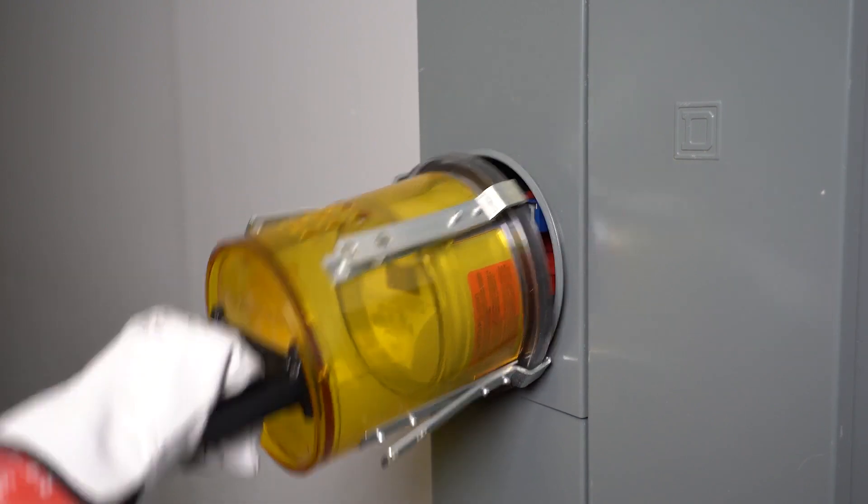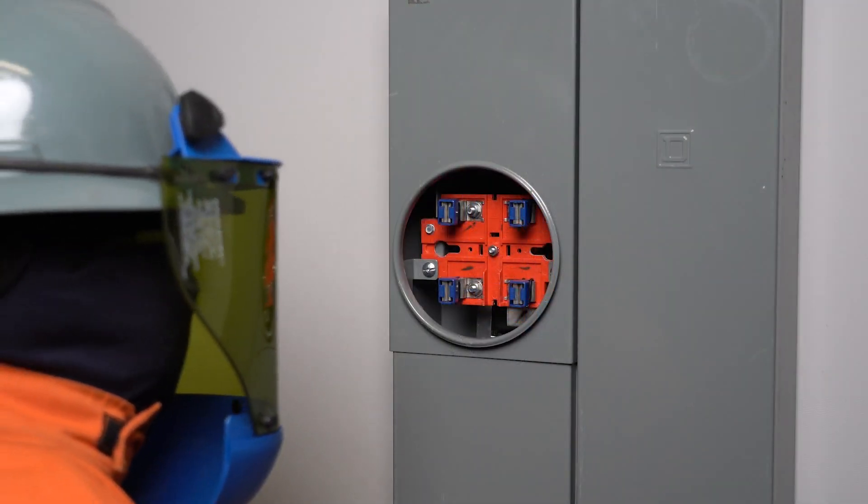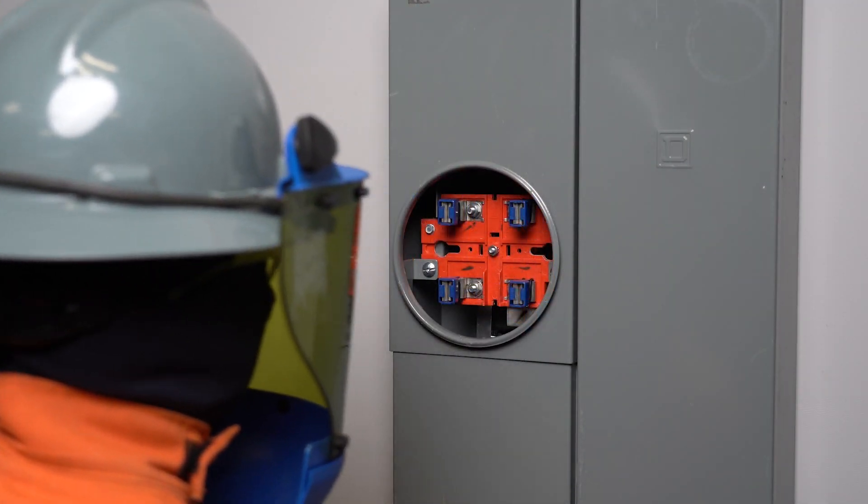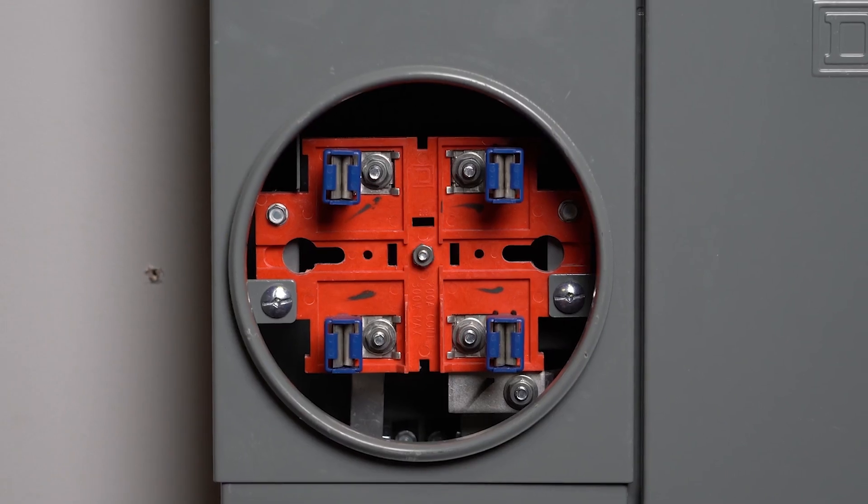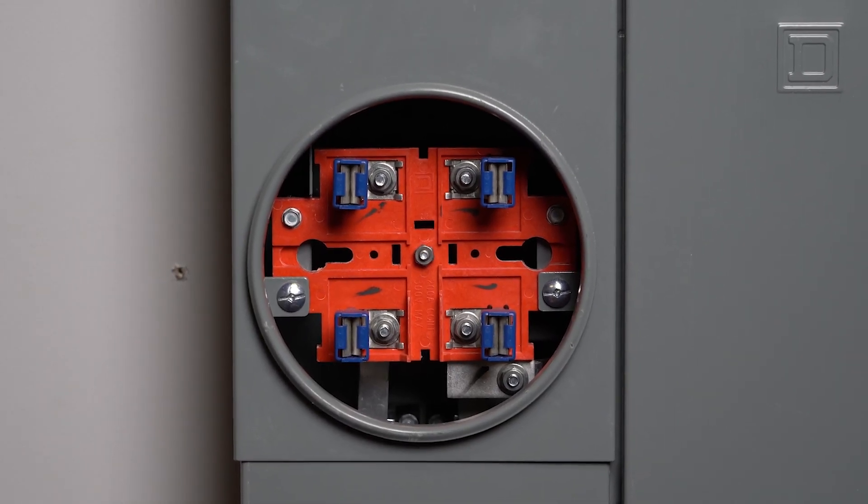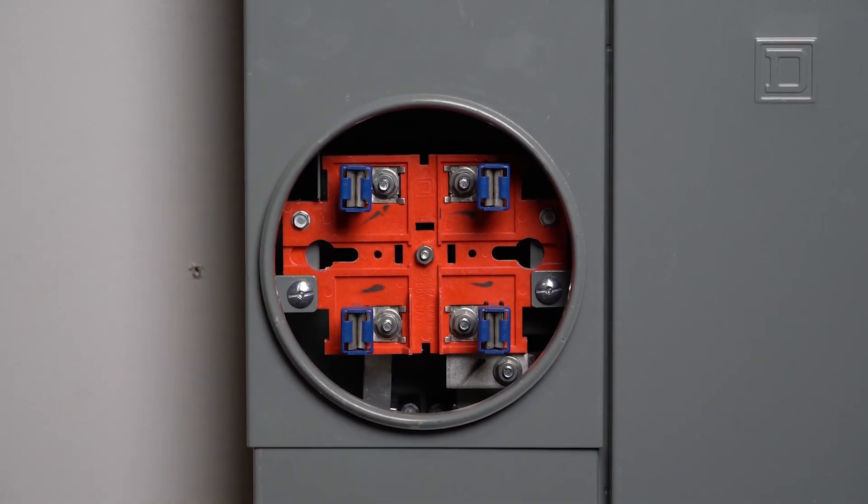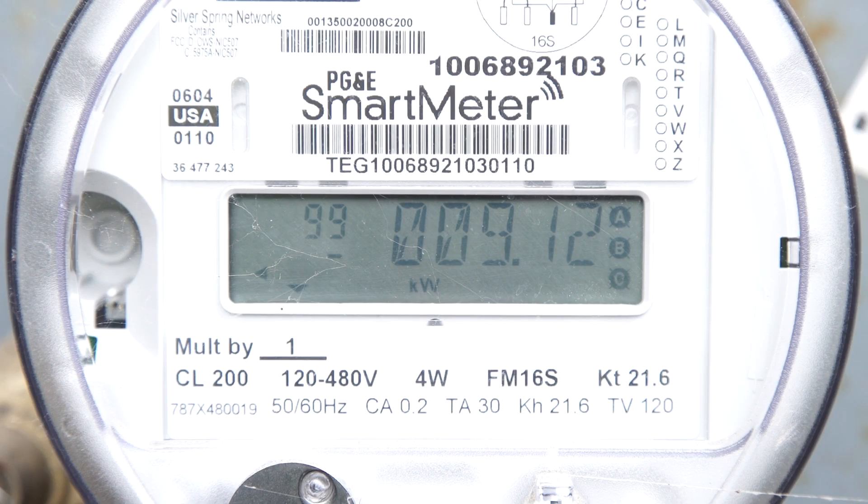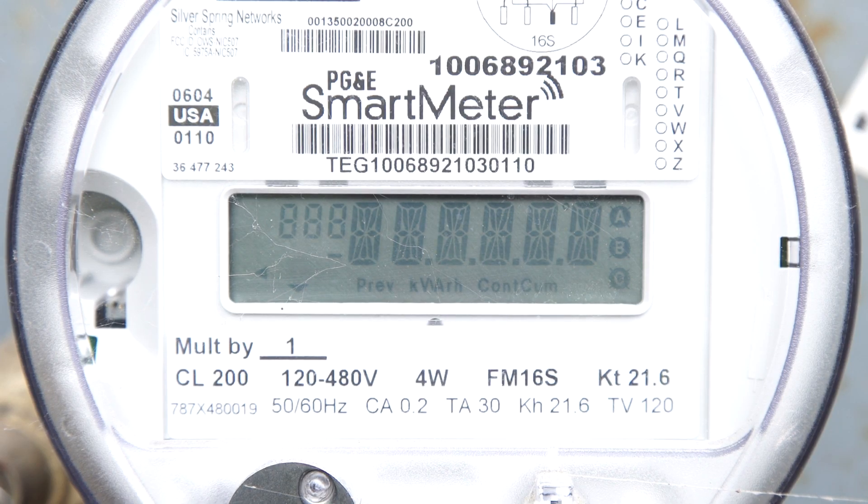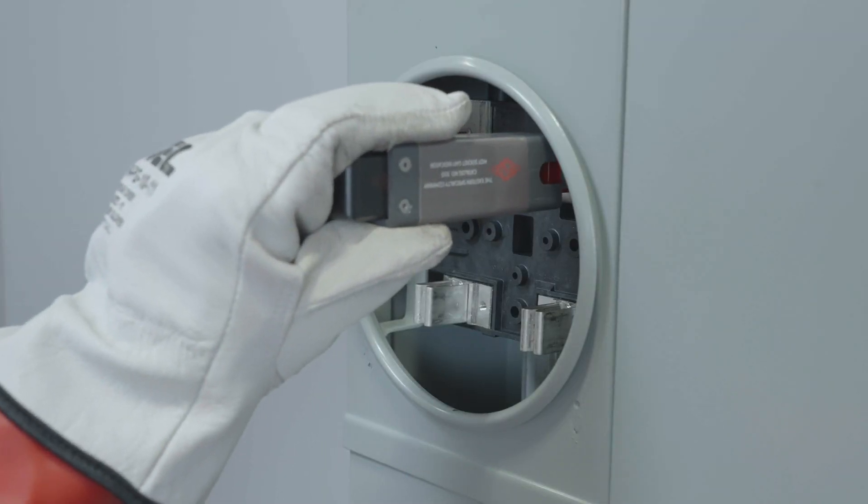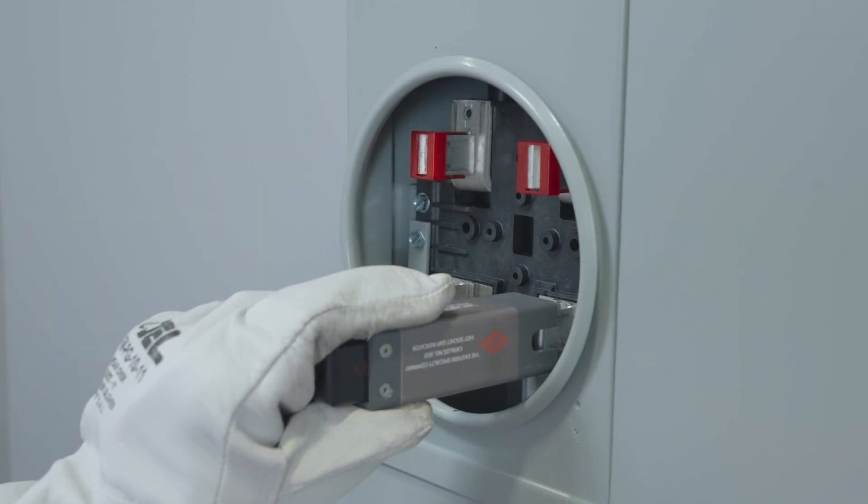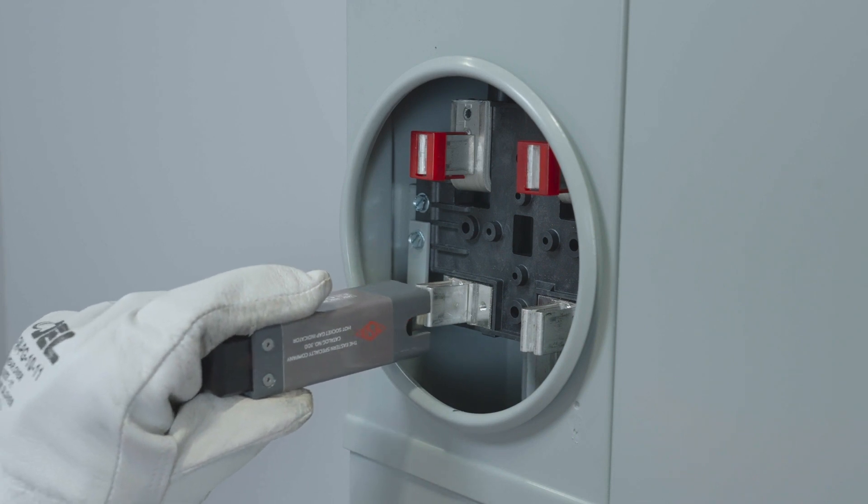Before installing Backup Switch behind the utility meter, ensure the meter socket is in good condition and is compatible with Backup Switch. Note that Backup Switch can only be installed in Type 2S meter sockets. Inspect the meter to confirm there are no signs of damage, arcs, or misalignment of the blades. Tesla recommends the use of a hot socket gap indicator tester to verify the integrity of the meter socket jaws.